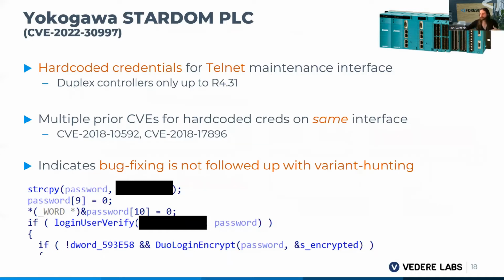An example of an incomplete rather than an improper bug fix would be the Yokogawa Stardom PLCs, which are very big in mining. They have a telnet maintenance interface that has had multiple prior issues with hard-coded credentials in 2018. Even though these issues were fixed, we found another set of hard-coded credentials affecting duplex controllers specifically. The fact that the same issue affecting the same interface, but in a slightly different part of the firmware, was left in there after fixing 2 similar cases, suggests that bug fixing was treated as a one-off—a bug gets reported, the engineer fixes that specific bug, and that is that. Rather than being followed up with variant hunting, where you look for other hard-coded credentials within the code base. That's the way you'd want to do it, but unfortunately that apparently hasn't happened here.